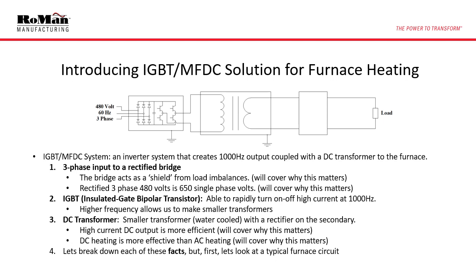This introduces the concept of high-efficiency, high-voltage power transmission. We then use an IGBT to rapidly turn on and off high current at 1000 Hz. This high frequency allows us to create smaller transformers. A transformer then produces the high current necessary to heat the furnace. A key portion of our value proposition is this high voltage transmission. When we rectify three-phase up front, we start with a higher voltage. That higher voltage allows us to step down the necessary voltage at a higher ratio. This correlates to lower current draw and lower peak demand. We then rectify the transformer output to direct current. As I will cover later in this presentation, direct current is inherently more efficient on many levels.